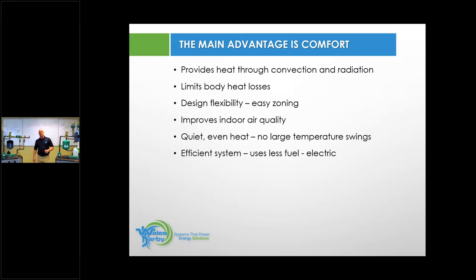I always joke around about this next one here, improve indoor air quality. And why do I say that? Well, we've been in a pandemic for over a year now, it feels like, and air quality is a concern to everyone. So do we improve air quality? No. But one thing we can do is, if I have a child that's homesick, I can isolate them in a room with hydronic heat, as long as I don't have an air handler, just baseboard heat. If I had a warm air system piped in properly with supply and return in each room, I would be pulling the germs from that room into the whole house every time that unit ran. So we don't improve air quality, but you can understand those characteristics there.